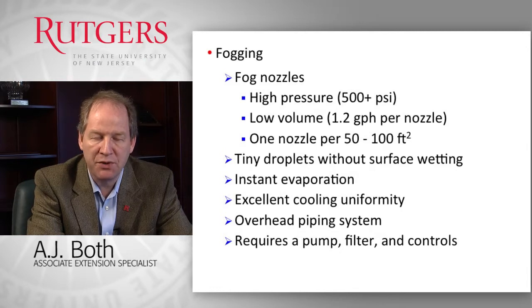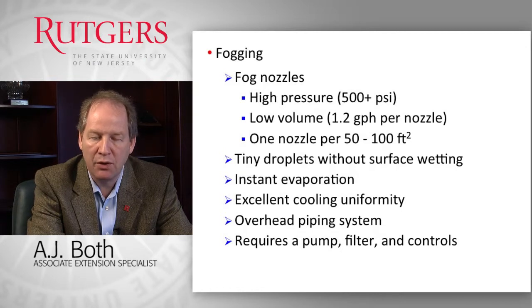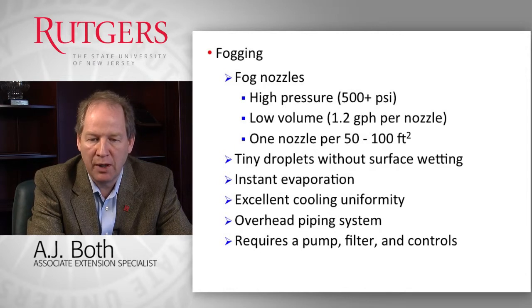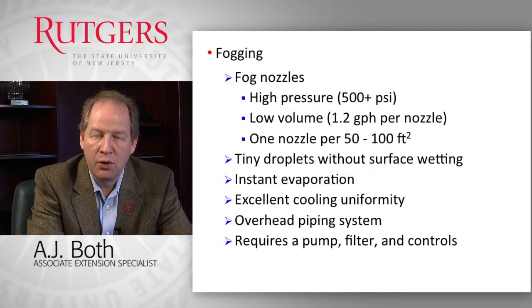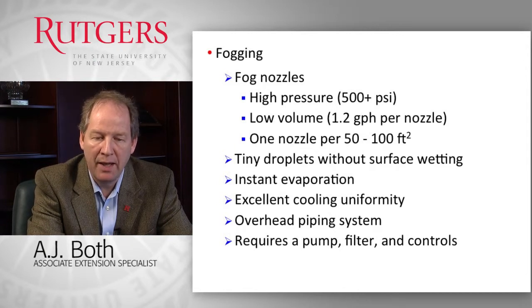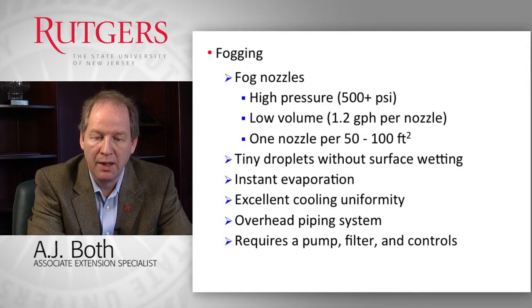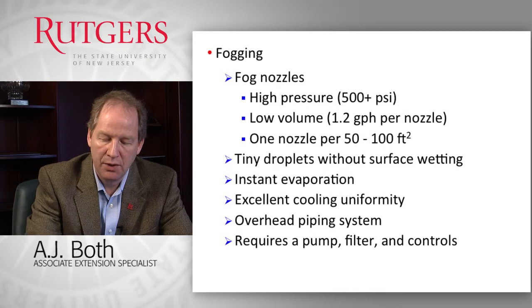Fogging systems use high pressures — 500 plus psi — with perhaps as little as 1.2 gallons per hour per nozzle of water flow. Similar to the misting system, we put one nozzle for every 50 to 100 square feet of growing area. This provides excellent cooling uniformity, as the nozzles are placed throughout the greenhouse environment, making it more uniform than a pad and fan system. An overhead plumbing system is required, along with a high-pressure pump. Filters are very critical because the opening sizes are very small, so you need very clean water, plus controls to operate the fogging system.